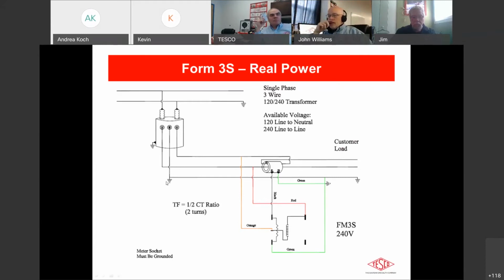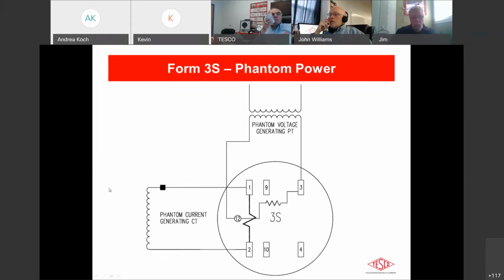Very good point, Jim. Thanks. So here again, because of the ability for a test board to vary both the voltage and the current according to whatever you want to see the meter read, you don't have to worry about those factors like Jim mentioned, other than that becomes part of the standard setup and what the computer produces to put out to the voltage and current transformers out to the meter socket.